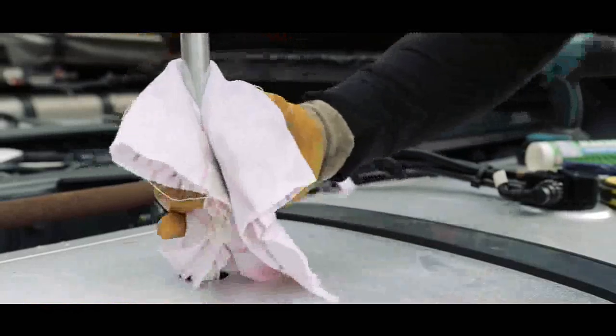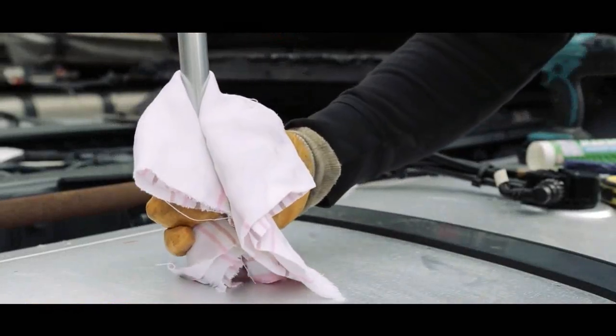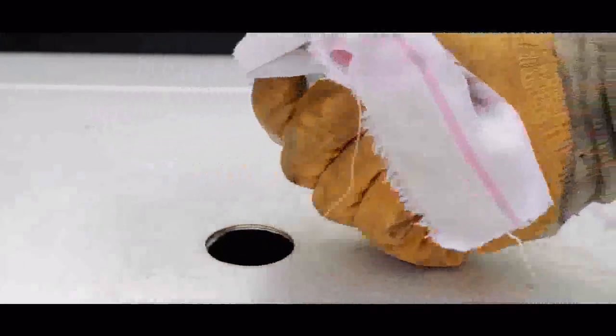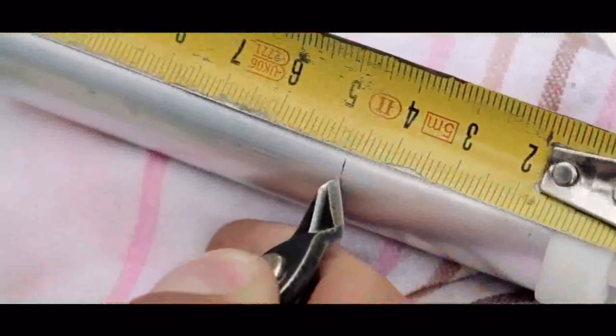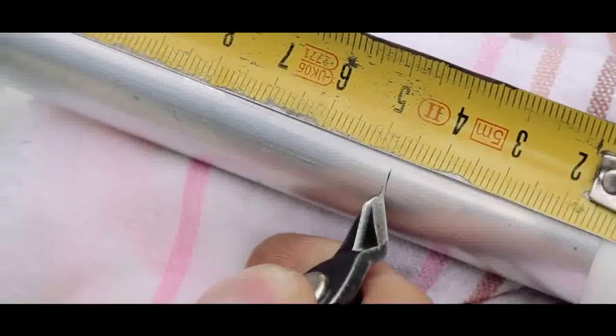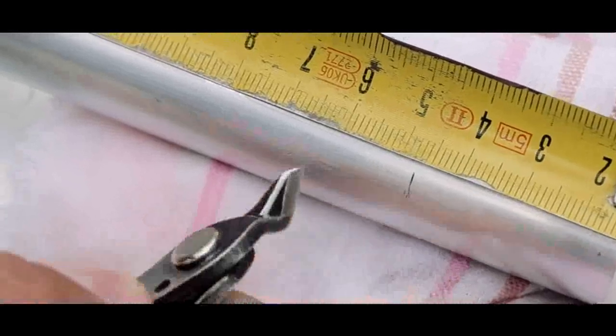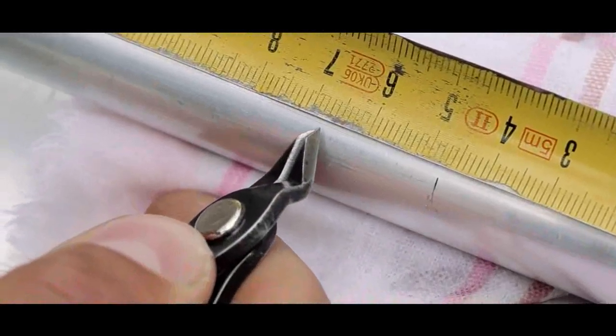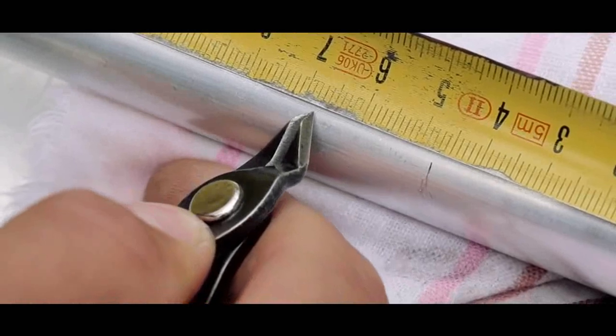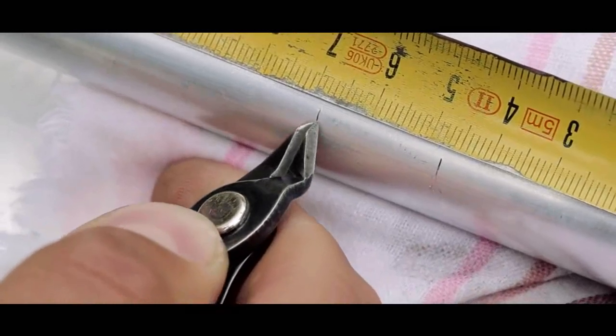Slowly pull the probe out of the fuel tank because it has diesel inside. While pulling it out, drain it with a cloth from the end of the probe. Note that the probe must be with the bottom cap. Mark the distance that was measured before and add 1.5 to 2 centimeters to it. Mark it again, and that will be the probe cutting place. The additional 1.5 to 2 centimeters are needed because usually there is small trash or water at the bottom of the tank.